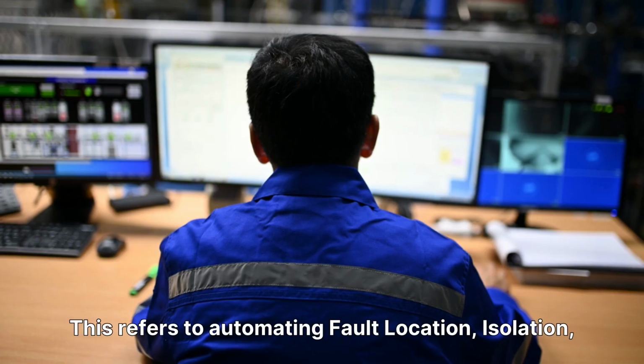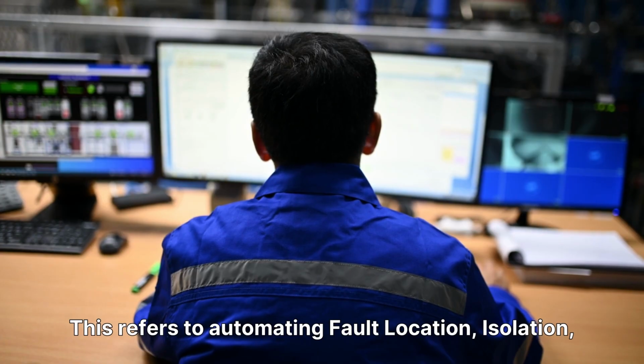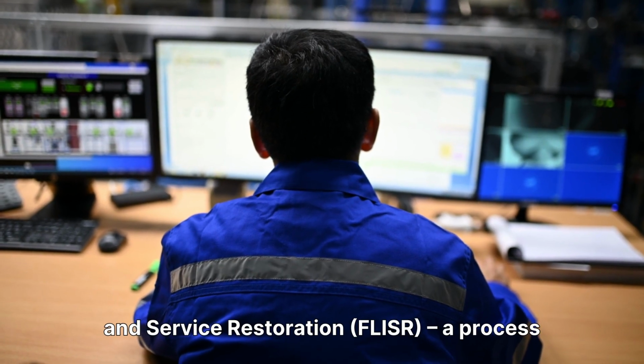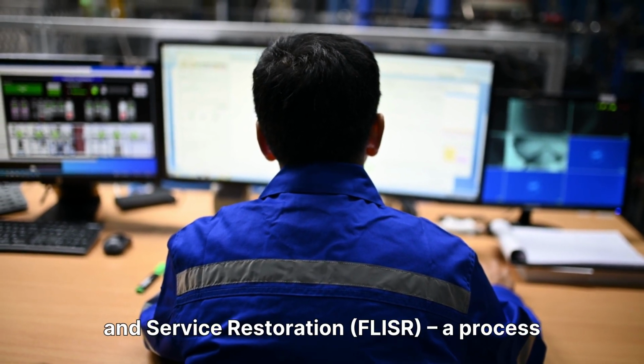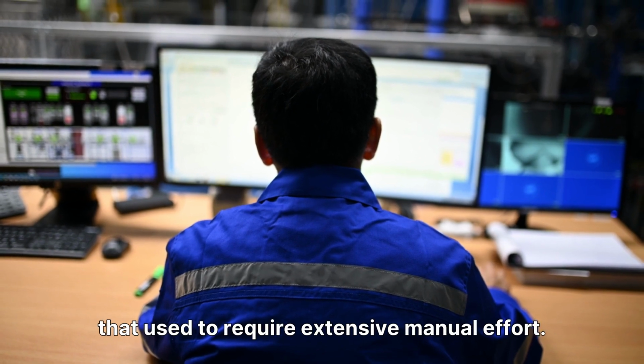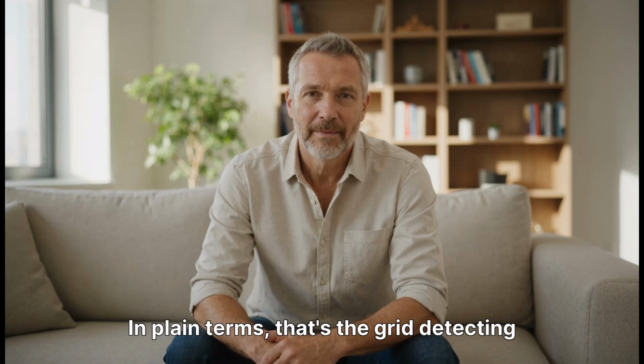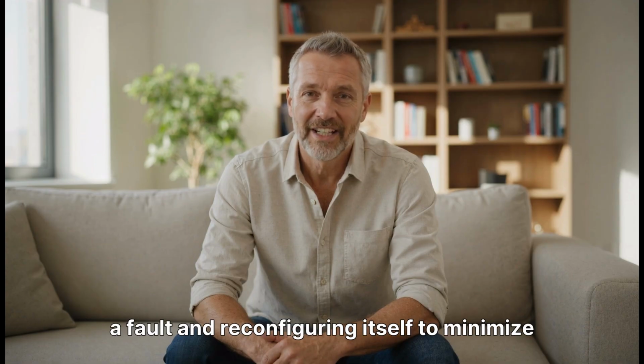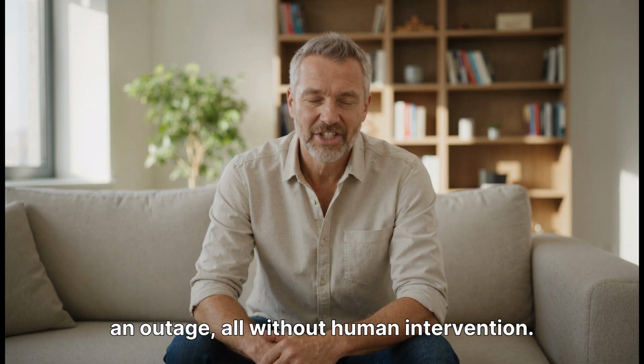Perhaps the most visible success of AI in the grid control room is the move toward self-healing networks. This refers to automating fault location, isolation, and service restoration, FLISR, a process that used to require extensive manual effort. In plain terms, that's the grid detecting a fault and reconfiguring itself to minimize an outage, all without human intervention.